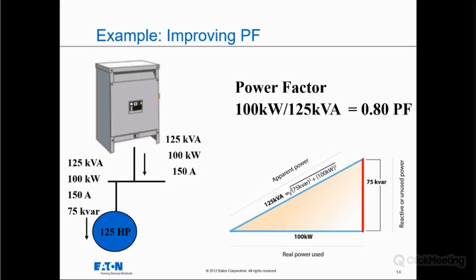So uncorrected, we see the power triangle on the right side of the screen. We have our 100 kW, the real work that it's doing. We see the 75 kVAR magnetizing power or reactive power that the motor wants to generate the magnetic field. And then we also see on the hypotenuse, again, what it's going to take in terms of total power to actually make this motor and this system work. If we look at it from a power factor perspective, you have 100 kilowatts divided by 125 kVA, that gives you a 0.8 power factor.